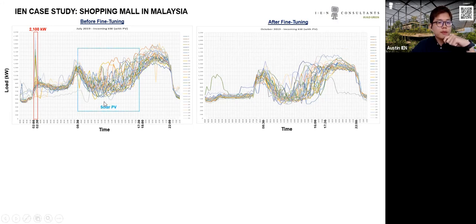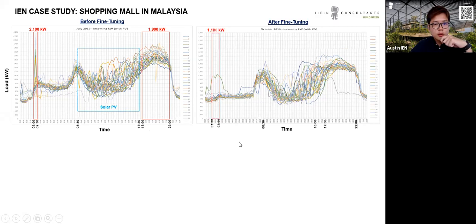During daytime, we have this solar PV and it lowers down the load. During nighttime or evening, the load increases again because there are more people going into the mall, and it reached until 1,900. So after fine-tuning, what is the result? We can see there's no more this unusual spike during midnight, but there was one day it reached until 1,100, which is still half of the initial load.